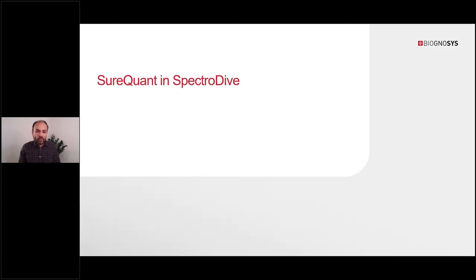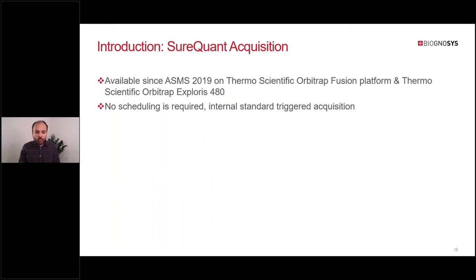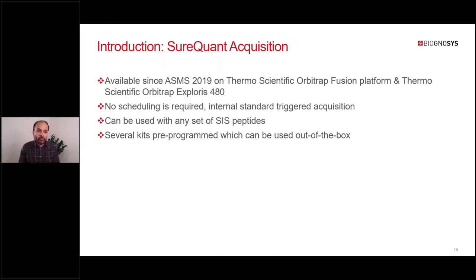That was a general introduction to SpectroDive and its key features. Next I will talk about SureQuant in SpectroDive. SureQuant has been available since ASMS 2019 on the Thermo Scientific Orbitrap Fusion platform and Orbitrap Exploris. The key selling point of SureQuant is that you don't need to do any scheduling, which simplifies targeted acquisition because it is based on internal standards triggering the acquisition of the endogenous target peptide. It can be used with any set of SIS peptides, and several kits are pre-programmed in the instrument software.